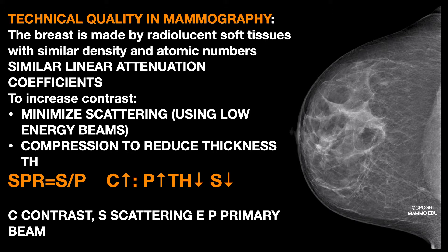Contrast is affected by the so-called SPR, scatter-to-primary ratio, which is the ratio between scattering energy S and that of the primary beam P. The contrast C improves with increasing the primary beam energy, and decreasing the breast thickness, and decreasing the scattering.